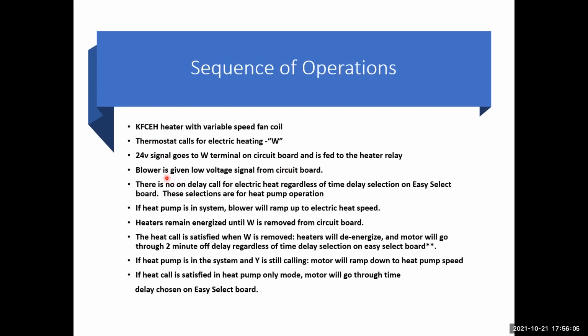Call from the thermostat W, 24 volt, goes on the W terminal on the circuit board and is fed to the heater relay. Blower is given a low voltage signal from the circuit board. There is no time delay on a call for electric heat, regardless of the time selected on the easy board. The selections are for heat pump operation. If the heat pump is in the system, the blower will ramp up to the heating speed. The heaters remain energized until W is removed from the circuit board. The heat call is satisfied when W is removed. Heaters will de-energize. The motor will go through a 2-minute off delay regardless of the time selected on the easy board.